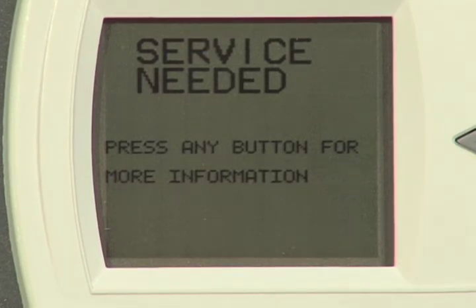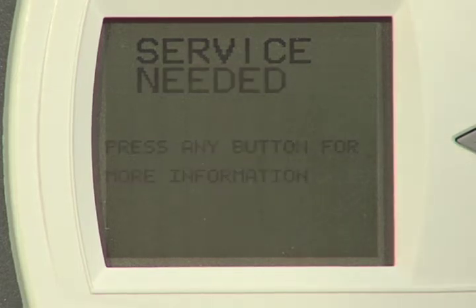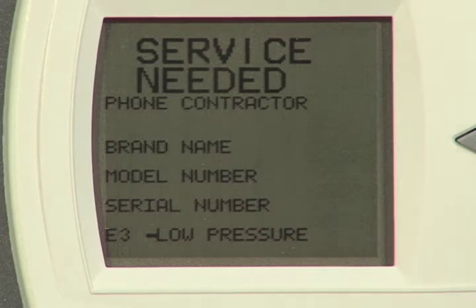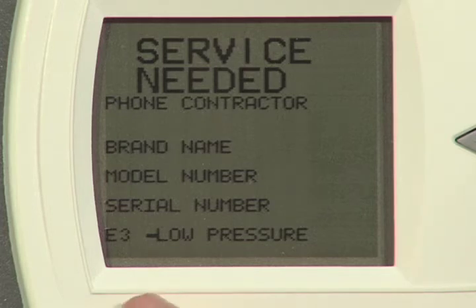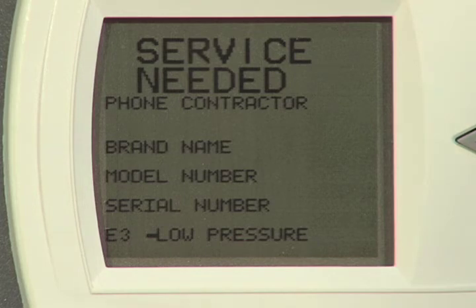The first screen that comes up is the service needed screen. We're going to press any button to continue. Again, the standard information: phone number for the contractor, brand name, model number, serial number, and then our actual fault condition here, which is an E3 low pressure fault.